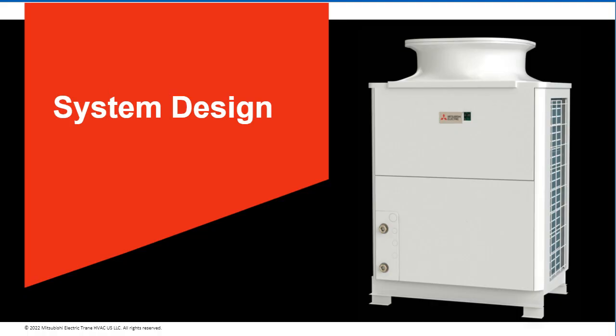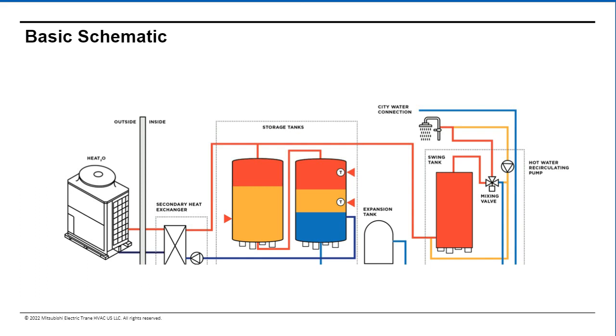Let's now transition to heat pump water heater system design considerations. Matt showed a similar diagram earlier, and I'm going to go into a little bit more detail here. The commercial heat pump water heaters get installed outside to reject cold air to ambient. From there, it's cold return water back to the hot water heat pump and hot supply water out to the building. Many systems utilize a primary-secondary setup like is shown in the diagram, where the hot water from the hot water heat pump circulates in a closed loop through a secondary heat exchanger.